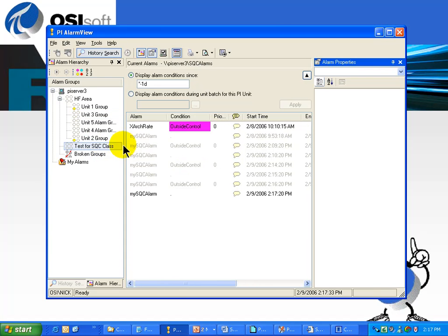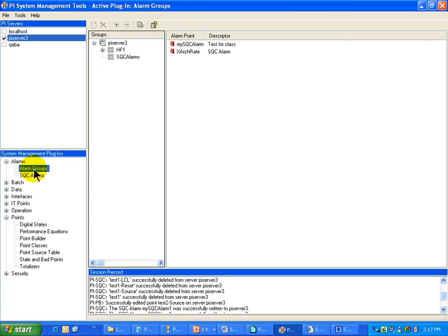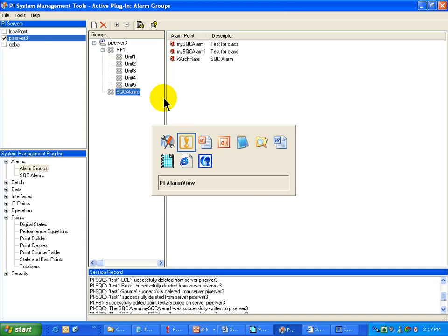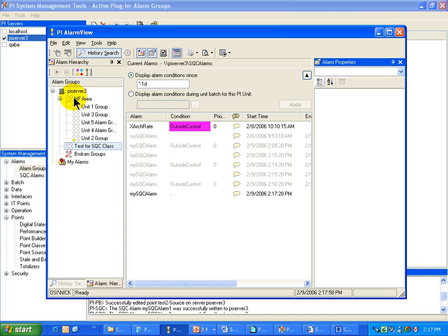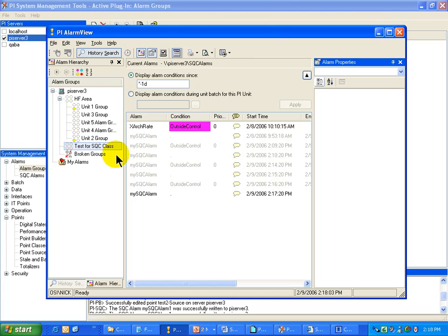I've chosen to create an Alarm Group for SQC tags, and I've done that in the PI System Management Tools. If we take a look at the Alarm Groups section in System Management Tools, you'll notice that I have an SQC Alarms Group. I've got this HF1 that has a number of children groups underneath it — Units 1 through 5 — which correspond exactly to what you see over here in these Units, which I can drill down through for my SQC Alarm Units.